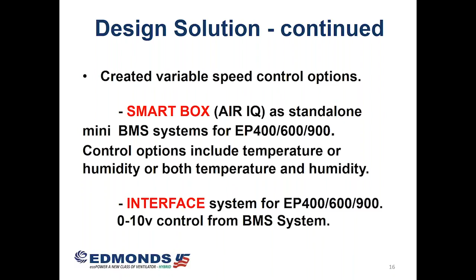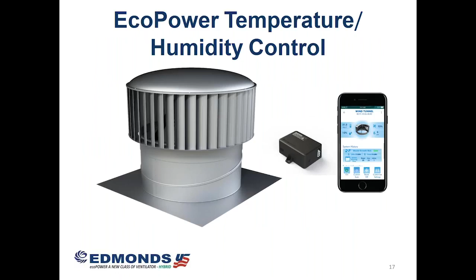Secondly, we can have a so-called interface box, which simply takes a Cat6 cable, providing 0 to 10 volt control from a centralized BMS. Often the BMS will have internal and external temperature feeds. An algorithm programmed into the BMS will determine how the vent operates. This slide shows the smart box controller, which is capable of Bluetooth control from an app supplied by Edmonds. The app will enable reprogramming of control settings. The standard setting, just enabling on-off control, remains an option there.